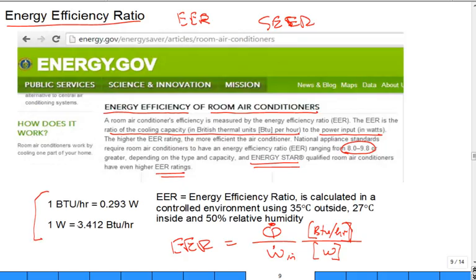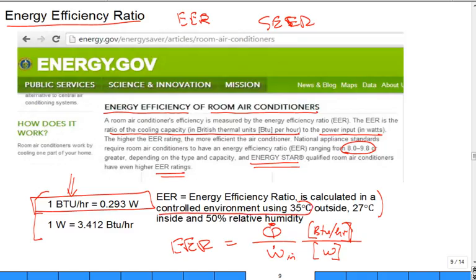These are two conversion factors — you don't need both of them. This will work. If I wanted to convert BTU per hour to watts, there's the conversion. Also, this is based on a controlled environment of 35 degrees C on the outside and 27 degrees C inside with 50% relative humidity. Why do they even quote the relative humidity? Because if you have higher humidity, you're going to have to condense more of that water vapor as you cool it.